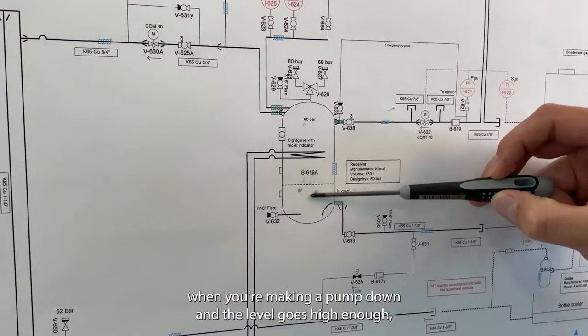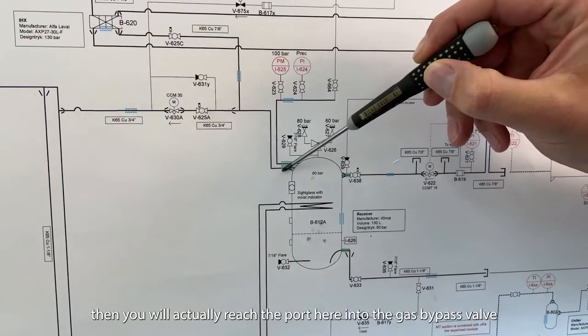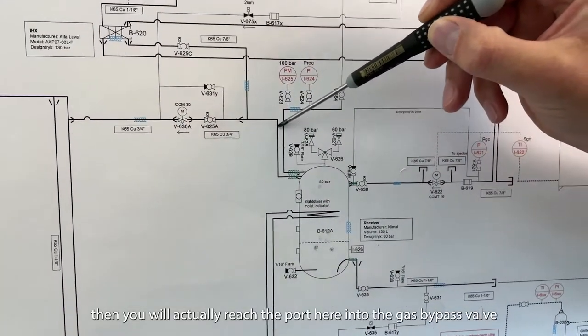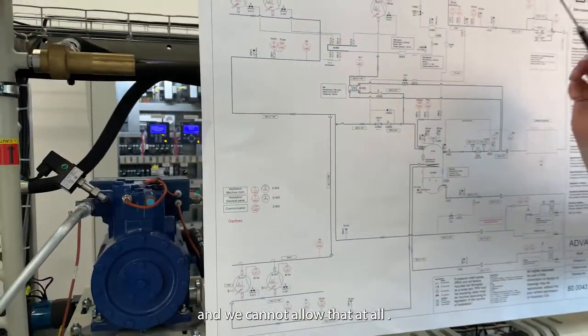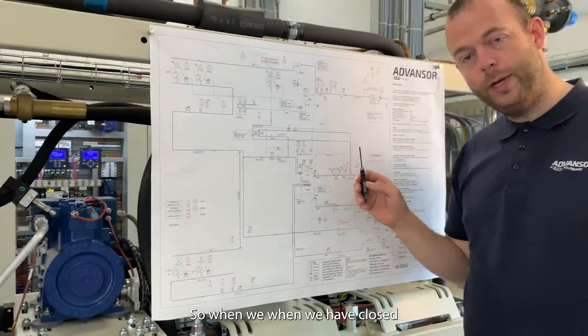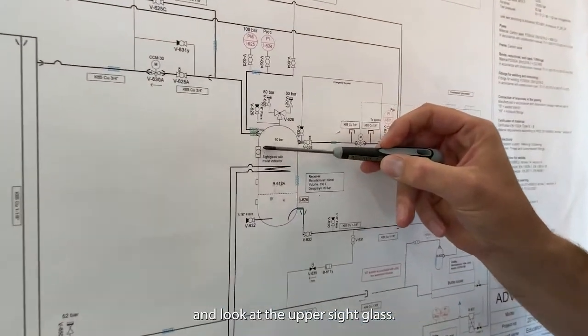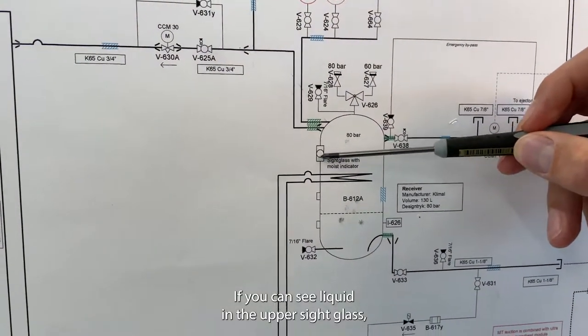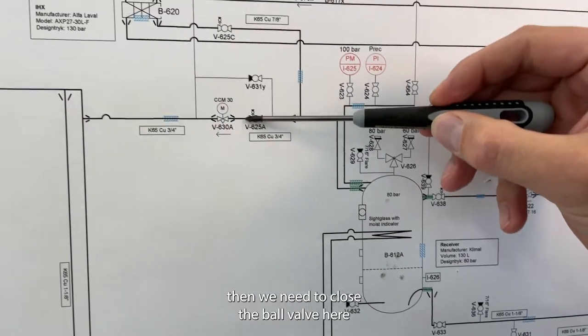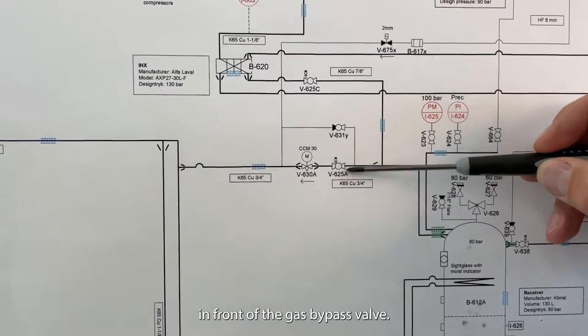When you are making a pump down and the level goes high enough, you will actually reach the port here into the gas bypass valve, and we cannot allow that at all. So when we have closed the valve here, we need to watch the upper sight glass. If you can see liquid in the upper sight glass, then we need to close the ball valve here in front of the gas bypass valve.